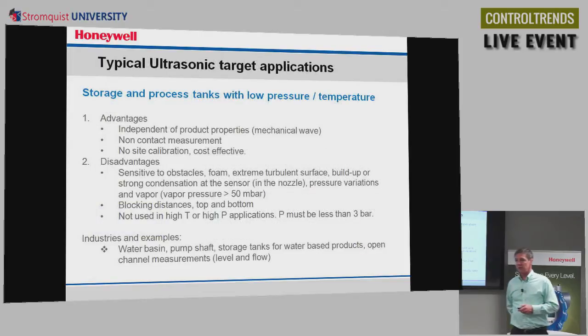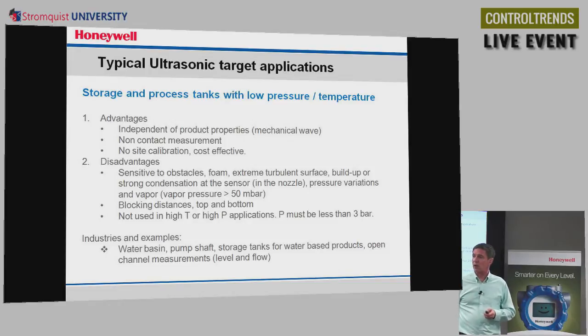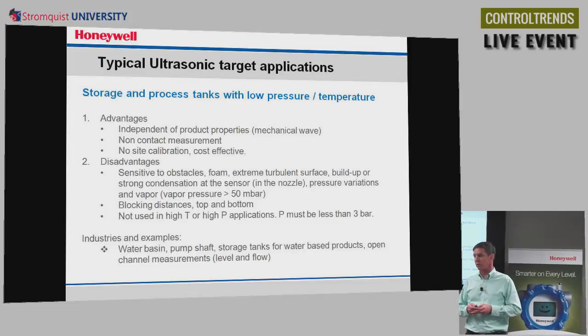So it's independent of product properties, so if the dielectric changes or the density changes, it doesn't matter. Ultrasonic can still measure it. It's not in contact with the process. So with our waveguide, we've got to be careful in case there's a corrosive kind of environment. We don't have any contact with ultrasonic. No site calibration required. However, it can be sensitive to things like turbulent surfaces and foam.